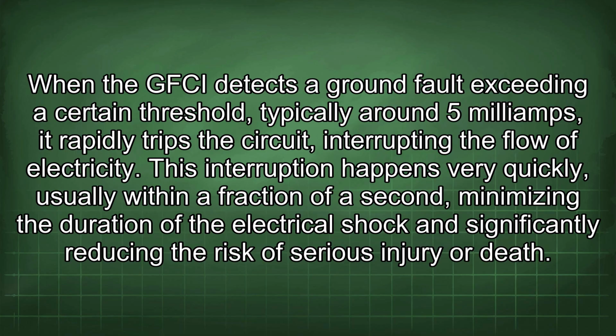When the GFCI detects a ground fault exceeding a certain threshold, typically around 5 milliamps, it rapidly trips the circuit, interrupting the flow of electricity. This interruption happens very quickly, usually within a fraction of a second, minimizing the duration of the electrical shock and significantly reducing the risk of serious injury or death.